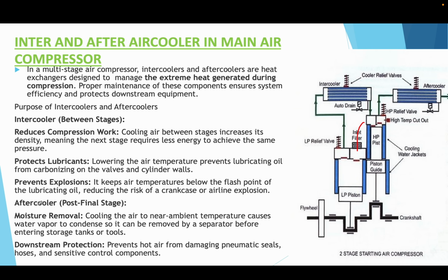Now, what is the purpose of aftercooler? The aftercooler is provided after the HP discharge and air bottle. The purpose of aftercooler is to make sure that the water condensate is removed. When the air is hot, it will have a high amount of water carrying capacity. After it has been cooled, the carrying capacity of water or moisture content will be reduced, and hence the mass of air will be more in the same volume.